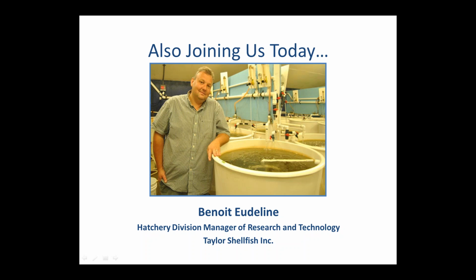And we do this to establish a slope, and I'm not even quite sure if it's a proper way, and then we calibrate the probe. So this calibrates the probe to what we call the NBS scale, and then we apply an offset with a sample cal on the UDA2182 using a Tris seawater buffer, and this shifts the probe to the total scale. And again, this step for us can be a problem, because sometimes when we do this shift, we observe the expected 0.15, 0.17 pH drift. In other words, when you switch from the NBS to the total scale, the pH goes down, which is expected.